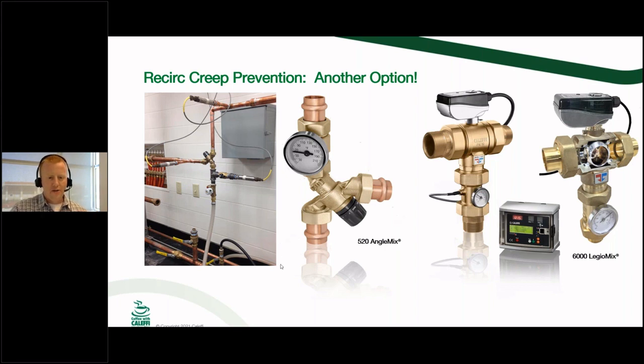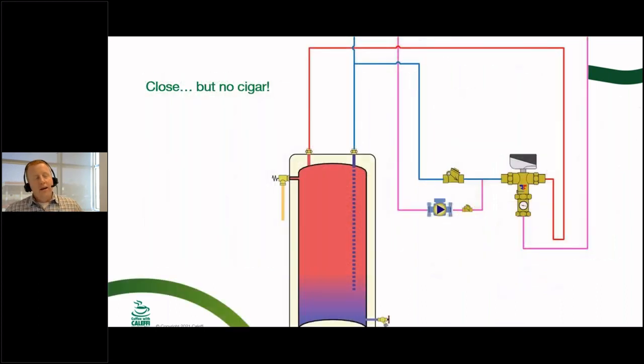But we had an interesting scenario here just recently. Let me see if I can go to the next slide there. Perfect. We had an interesting scenario where we weren't running into recirc creep, but we were running into the complete opposite. Instead of recirc creep, where it was creeping up in temperature on that loop, during times of no demand, they were actually running into problems where the loop temperature would drop. Okay, and obviously that's a problem as well. If you've got a big distribution system and that recirc temperature drops and drops and drops, and then sooner or later somebody starts opening fixtures, and it takes a long time for the hot water to get there, you're going to run into some unhappy occupants in that building.